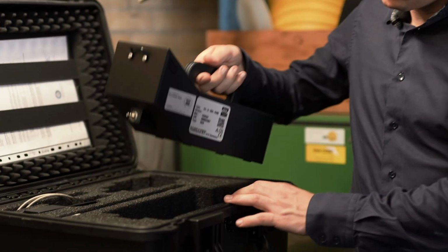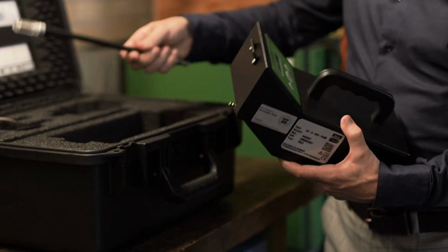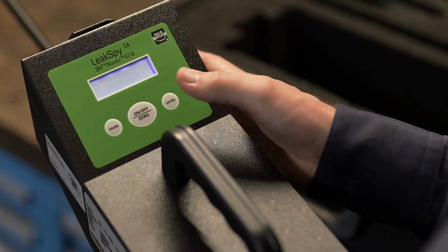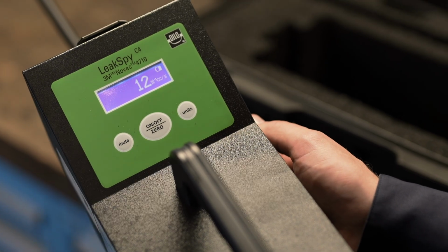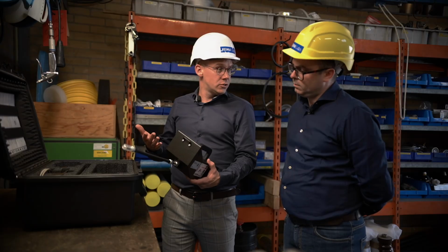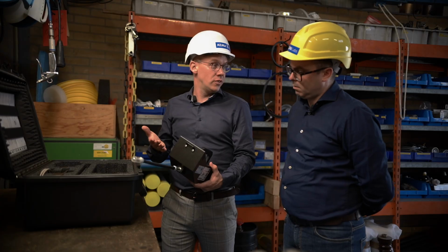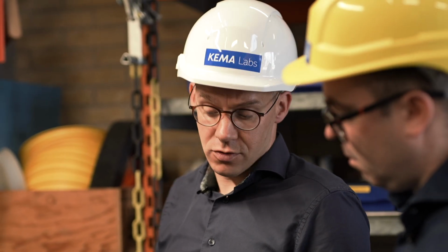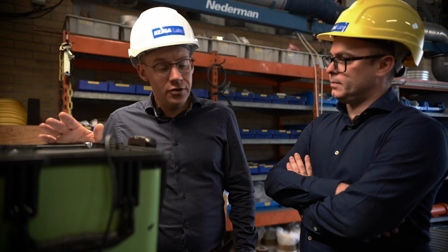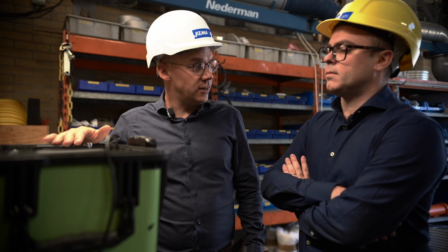One of the devices we bought is our leak spy, because during this entire cycle, of course, it is important that no leaks are present when we are handling the gas, and we should be able to monitor. So we bought a leak spy in order to verify this. It can also perform a test, because one of the tests we could perform with this is a gas leakage test over time. So it has multiple purposes, but this is mainly related to safety. Great. Another device we've bought is this multi-gas analyzer.